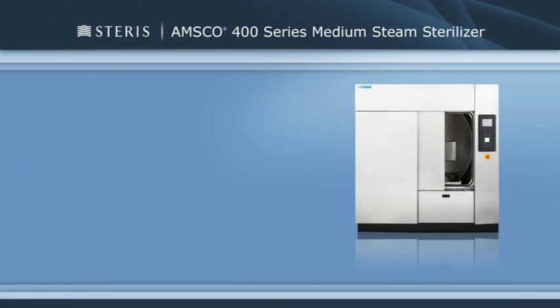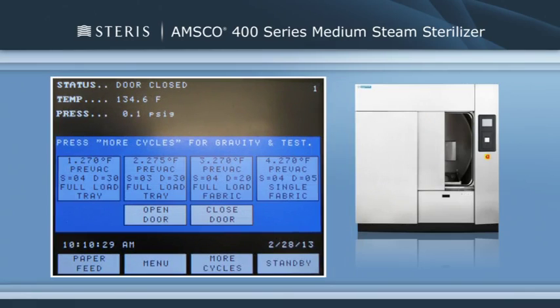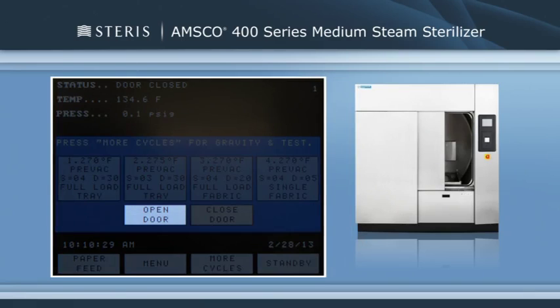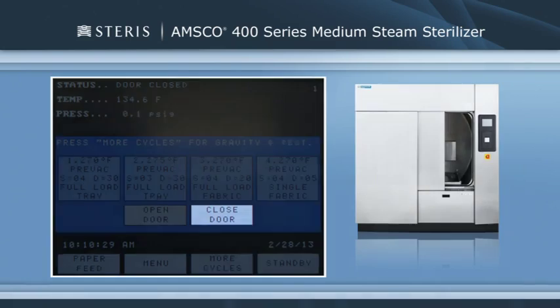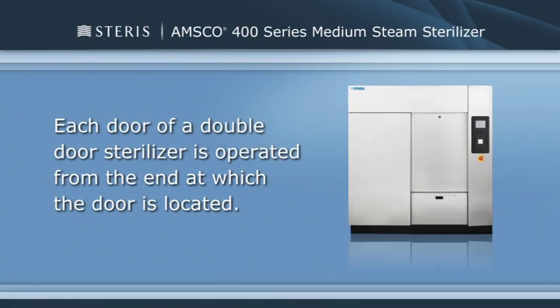In a horizontal sliding door orientation, the sterilizer door is operated using push buttons near the sterilizer control screen. Pressing the open door push button while the door is in the closed position causes the door to open. Pressing the close door push button while the door is in the open position causes the door to close. On double door units, there is no control of the power door at the opposite end of the unit. Each door of a double door sterilizer is operated from the end at which the door is located.